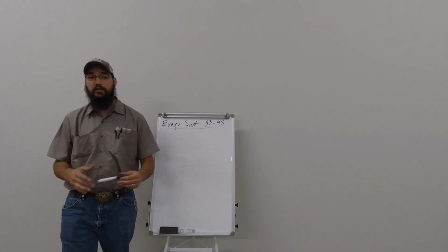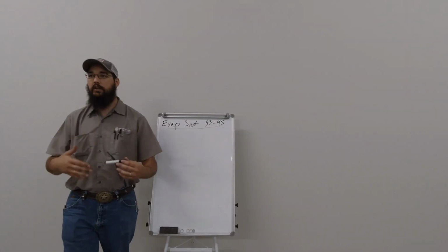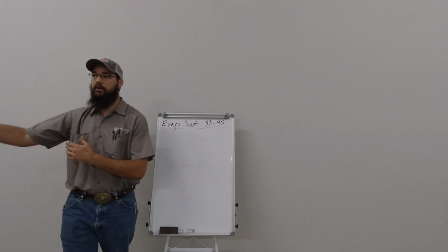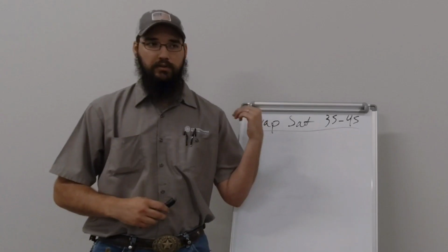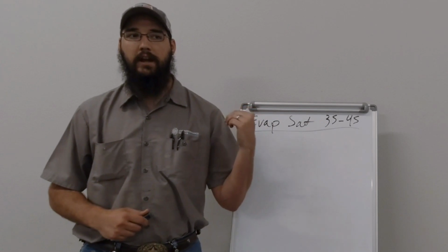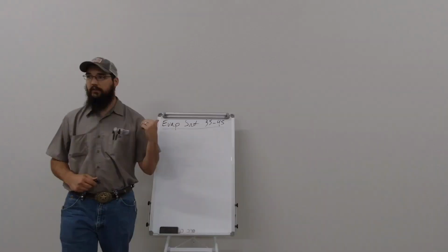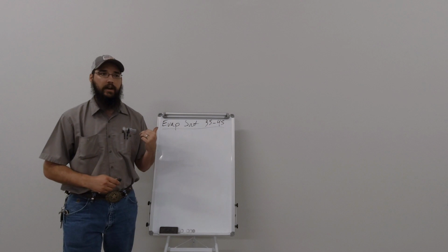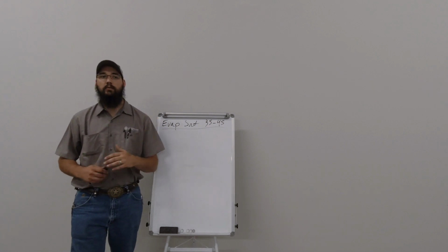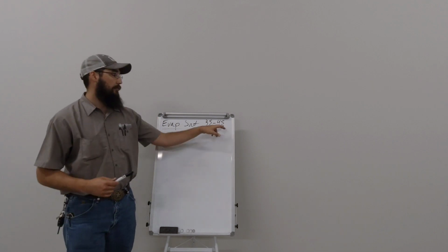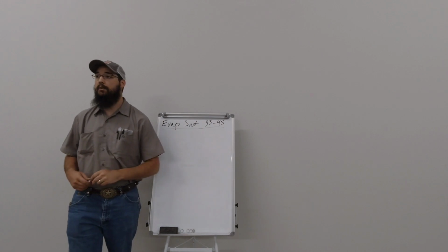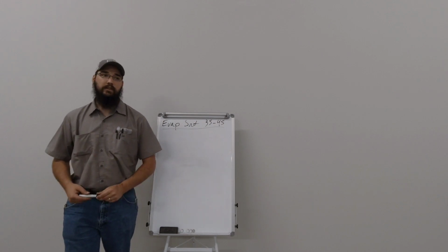The reason for that is you have to start factoring in the load. I don't want to get too far into the lesson with that, but when I start seeing below 38, I start asking a lot more questions. As long as I see at least 38, I'm a lot more comfortable with what that system is doing. Now 45 is a really great number as long as you're dealing with a standard system.